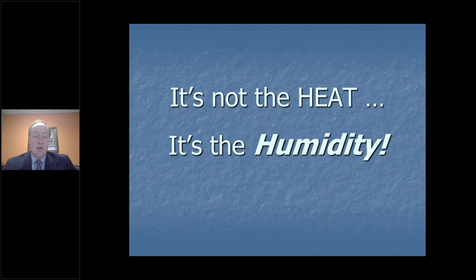to the latent load. So most of the time when I see buildings that say, oh, we put in new equipment, this is more efficient, but I'm having problems. We had a 15-ton rooftop unit and we have a new 15-ton rooftop unit, but I'm having moisture problems within my building. So I had to add a dehumidifier. That's a common problem that I see quite often. So yes, you have saved some energy dollars because you have a more efficient piece of equipment, but hopefully you've saved enough in your energy to buy yourself a nice dehumidification unit.